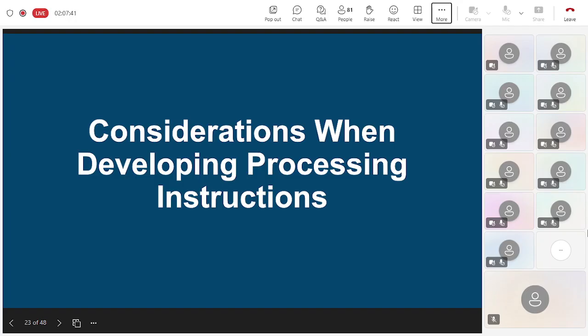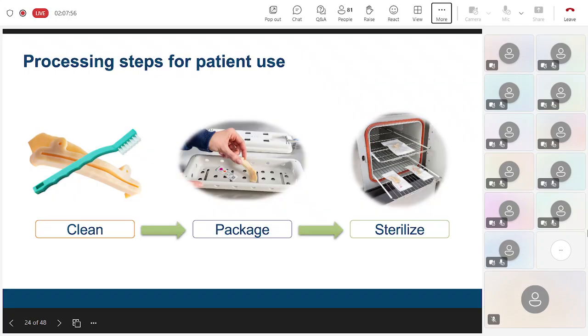So once the quality management system has been shored up, it's time to develop processing instructions that work for both the CSSD and the point of care 3D printed medical device. So we have processing steps for patient use. And when we think of sterilisation, we envisage the three-step process with each step having multiple tasks. Cleaning is the first step in the processing of medical devices for patient use. And this should not be confused with post-processing of the 3D printed medical device. So remember I said after the device is printed, it needs to be cleaned and then it needs to be finished correctly and sometimes cured with UV light. So that is what we call post-processing and is not to be confused with the cleaning process.